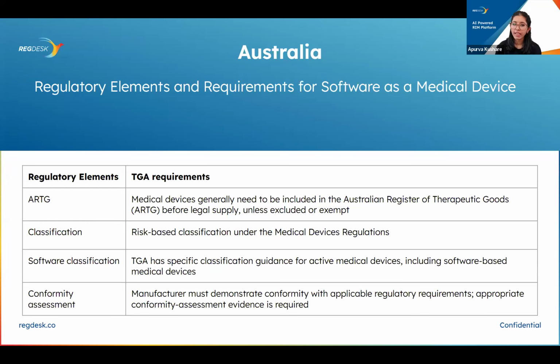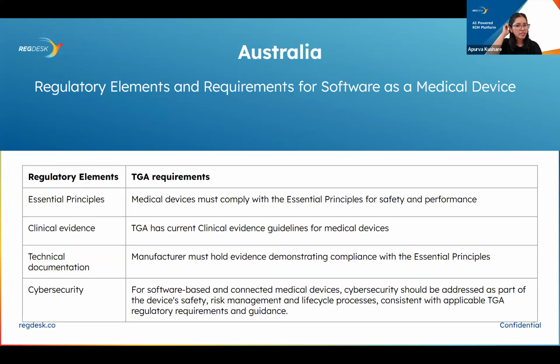The classification is again a risk-based classification under the MDR. So the manufacturers must consider all the classification rules in classifying their medical devices. And when more than one rule applies, the device must be classified at the highest applicable level. TGA requires evidence that the appropriate conformity assessment procedures have been applied and that the device complies with the essential principles. So these are some key details to consider.